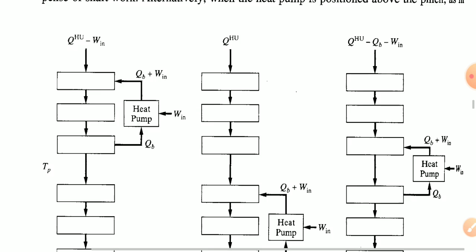Alternatively, when the heat pump is positioned above the pinch, as in Figure 10.50a, the compressor load, work W in, reduces the hot utilities load by this amount but does not reduce the cold utilities load. In this case, expensive power is converted directly to less valuable heat to reduce the hot utilities load.